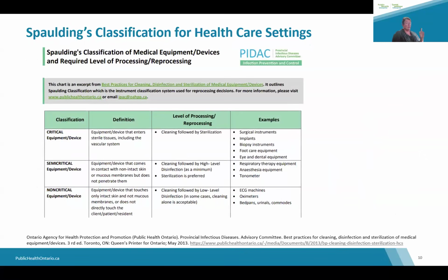So now we're going to shift gears and we're going to look at reprocessing. I think you're all probably familiar with Spaulding's classification, so we'll just go through this very quickly. First, we have critical equipment, and this is defined as equipment or devices that enter sterile tissues, including the vascular system, and they are to be cleaned, followed by sterilization. Semi-critical equipment, these are ones that come in contact with non-intact skin and mucous membranes, but do not penetrate the mucous membranes, and they are to be cleaned. They can be followed by high-level disinfection as a minimum, but it's preferred that they are cleaned and then sterilized, if you will allow. And then there's non-critical equipment, which is equipment that only touches intact skin and does not touch mucous membranes, or maybe doesn't even touch the patient. And this is to be cleaned, followed by low-level disinfection.